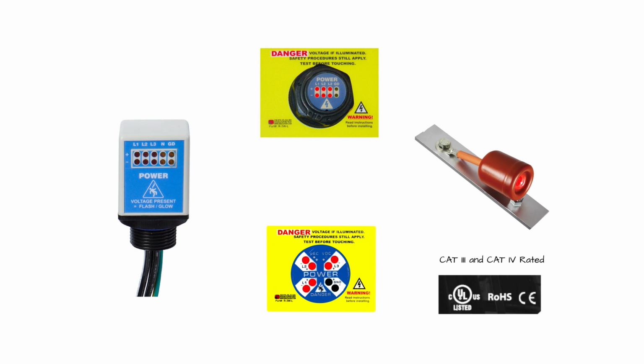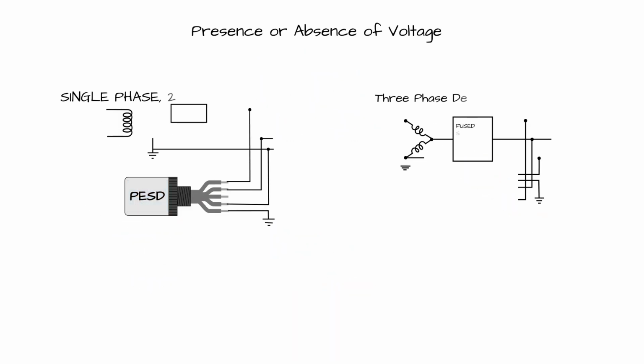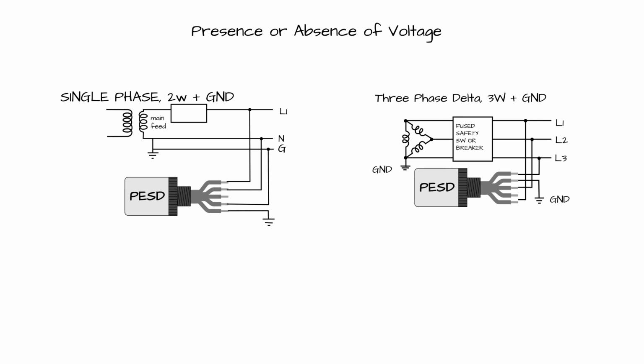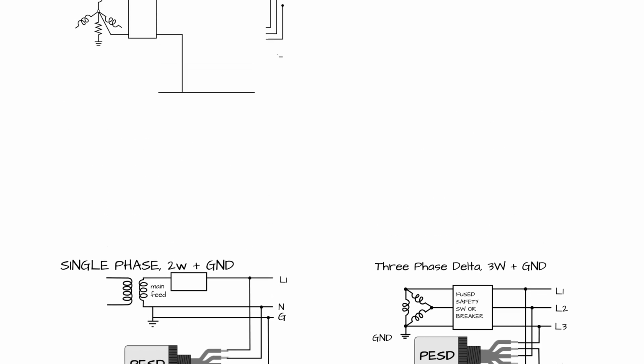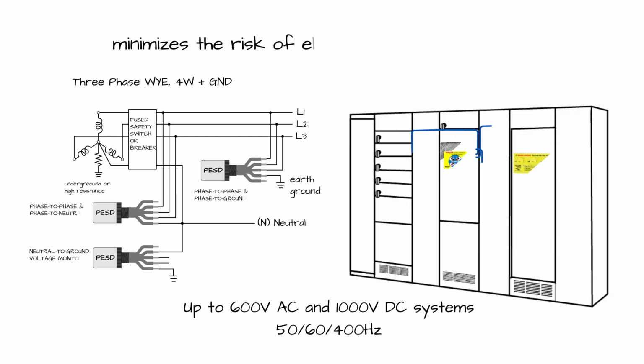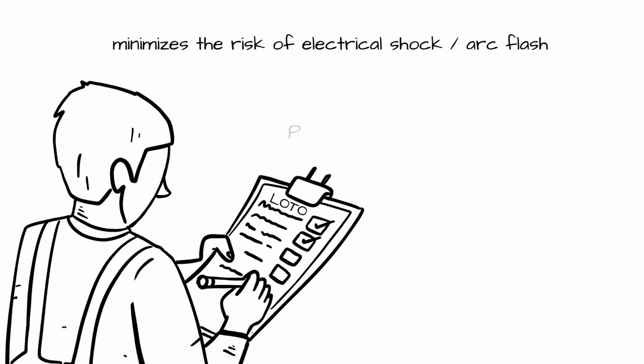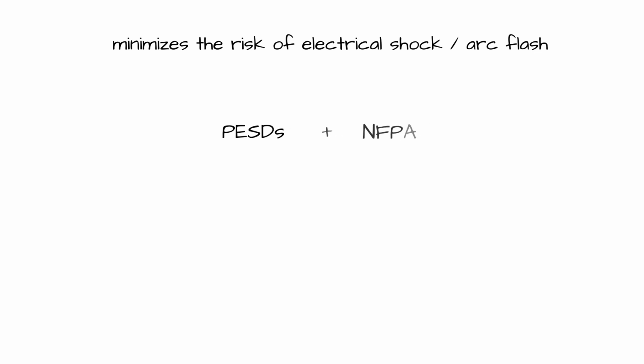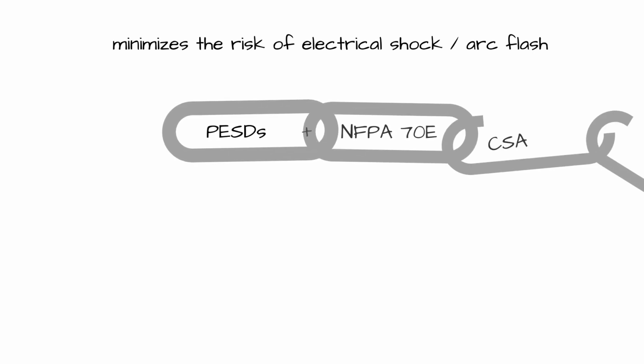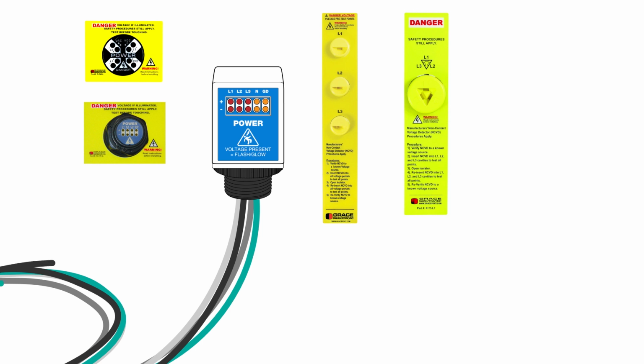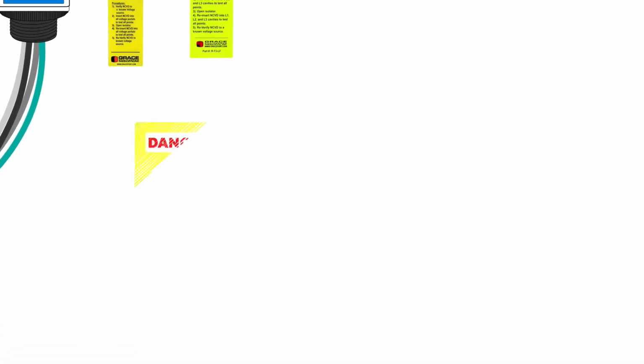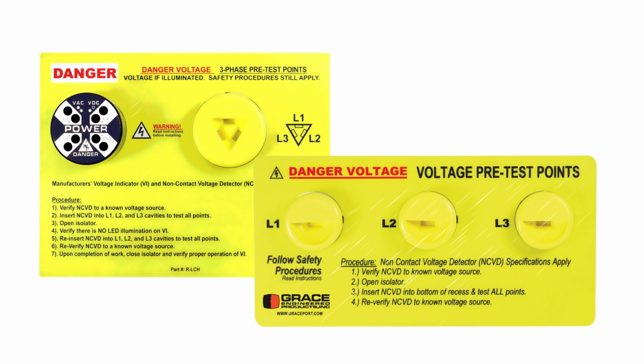These high impedance protected Cat 3 and Cat 4 rated and UL listed PESDs provide the means to safely verify presence or absence of voltage, either phase to phase or phase to ground, in both AC and DC systems up to 1000 volts, without exposing the worker to arc flash or shock hazards. When properly incorporated into a facility's electrical and mechanical lockout-tagout procedure, PESDs enhance compliance with NFPA 70E, CSA Z462, and OSHA energy isolation principles. All of our PESDs can be combined in several available standard and custom configurations for either door or flange mount installations, as well as with procedure labels to further reduce the task risks to bare minimal levels.